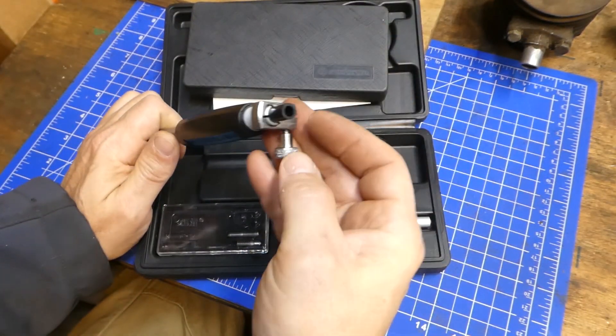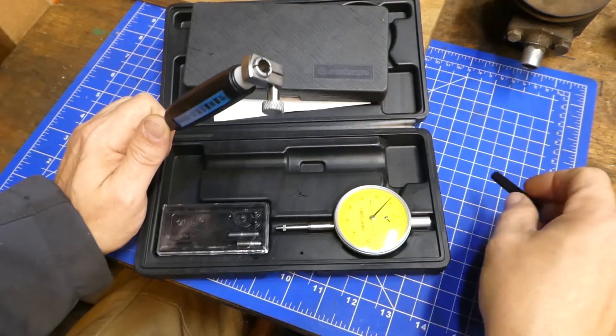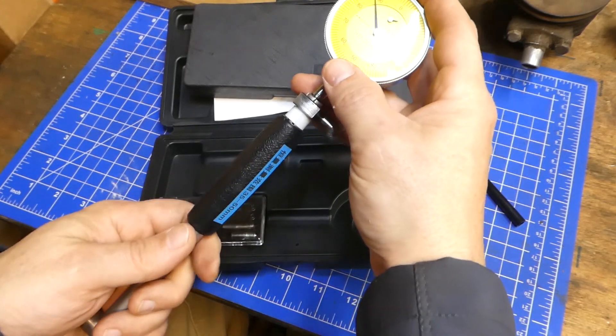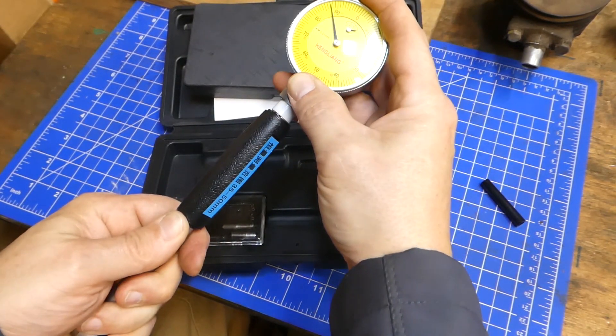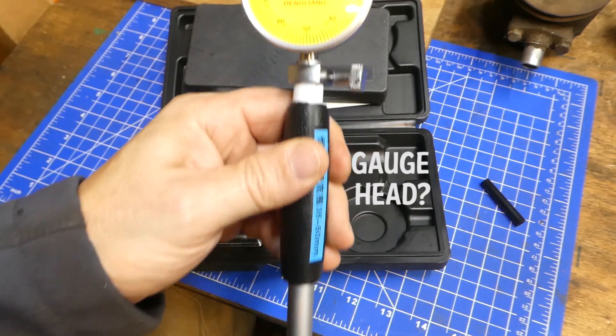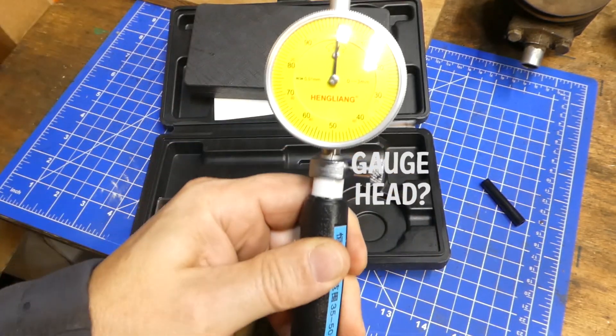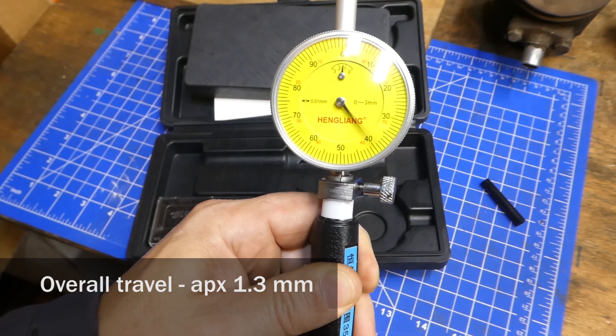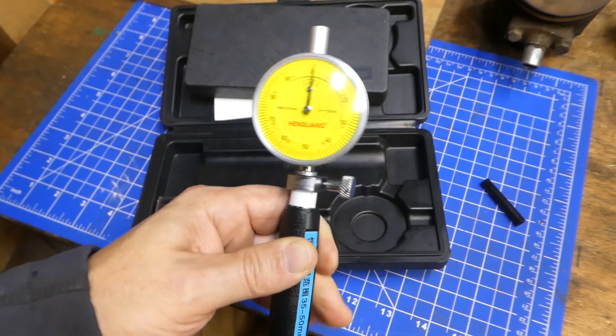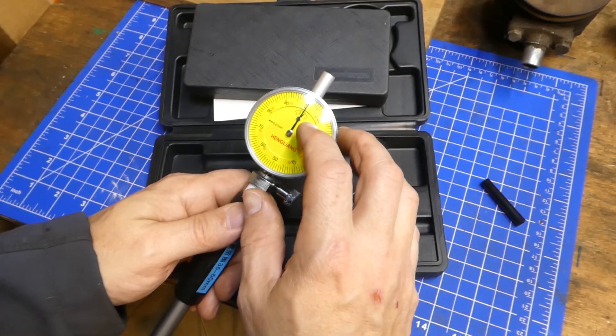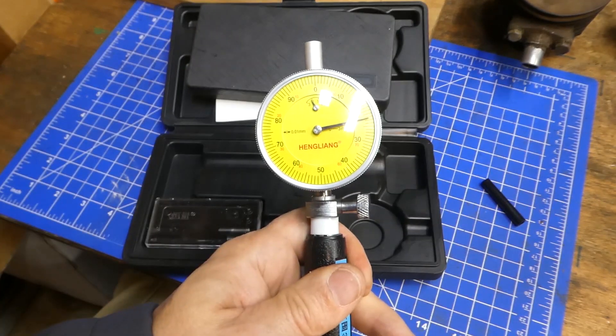Let's put it together here. We're going to take out this little cap that's in here. This is just a cap to keep debris out. Stick our indicator head in until it moves. So the total travel of the micrometer head, which is what I'm pressing down here, is approximately a millimeter and 3 tenths. Maybe a little bit more depending on how hard you squeeze it. The dial indicator is actually pretty smooth. It's pretty good. It does have a rotating bezel so you can line it up.